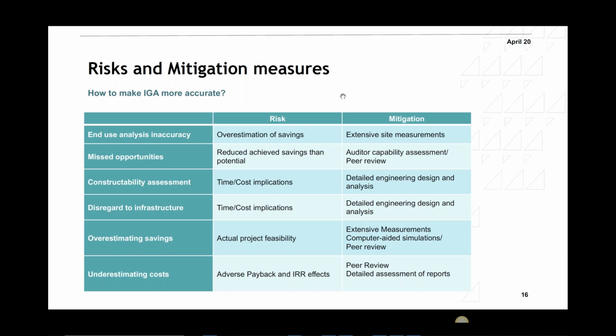Constructability assessment: sometimes the auditor or ESCO comes up with an idea that isn't buildable, so we need proper detailed engineering analysis as mitigation. There's also disregard for infrastructure - sometimes the ESCO or energy auditor proposes something that disregards the infrastructure, and it won't work without the proper infrastructure in the building. We faced that once when they were adding VFDs on some panels, and there wasn't proper grounding because the building was very old, so whenever they turned the VFDs on, it would trip.